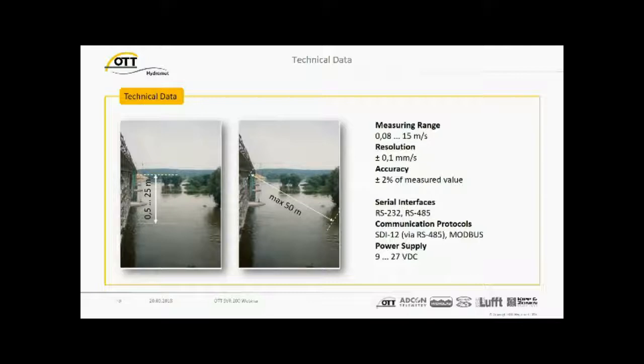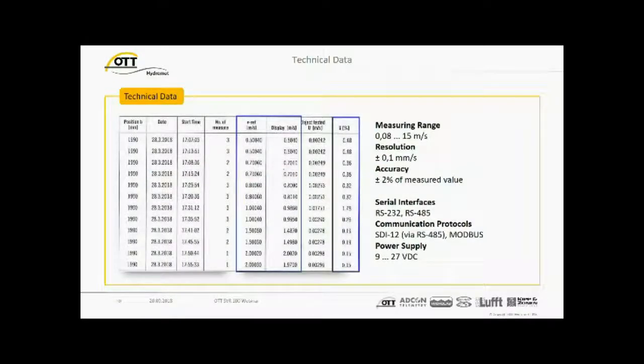Technical data, very important. What can we expect? The velocity range is very wide. 0.08 meters per second up to 15 meters per second with a resolution of 0.1 millimeter per second. The accuracy is plus minus 2 percent of the measured value. So you will think, oh, that's good. How do they guarantee us this? We have been with the sensor in a laboratory in Switzerland, which is METAS, the biggest and I think also the oldest laboratory for hydrometric calibrations we have here in Europe. And we got a certificate for it.